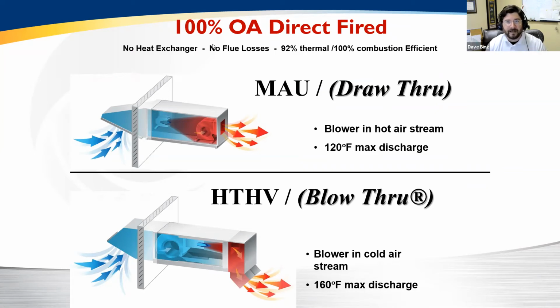If we think about what HTHV is, we are probably more familiar with a typical draw-through direct-fired makeup air unit. These are typically higher CFM, lower delta Ts, where I'm drawing the air across the burner. Because my mechanical components are in the hot airstream, I'm typically limited in discharge temperature, because bearings, motors, belts, and pulleys don't like to be in these extreme temperatures. But they both have 100% outside air, they both have 100% combustion efficiencies, they both have no heat exchangers, and they both have no flue losses.